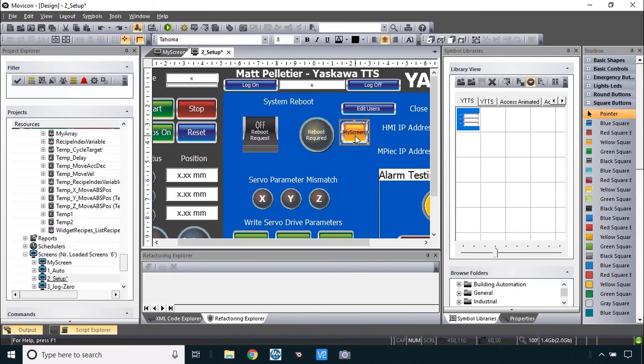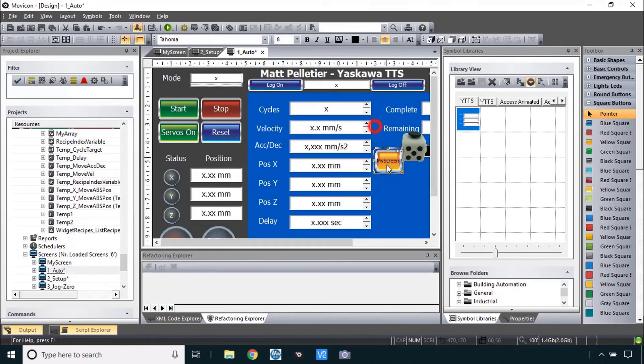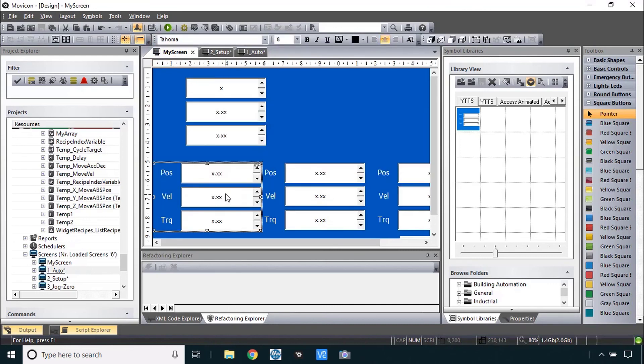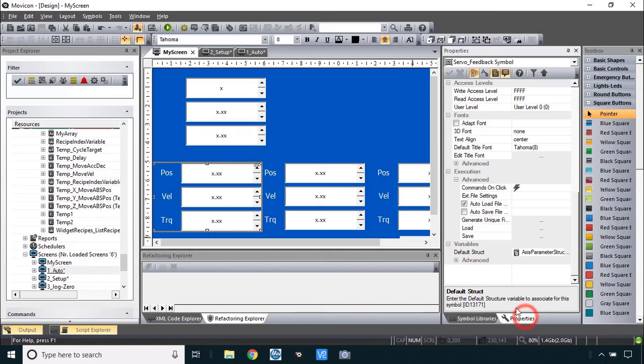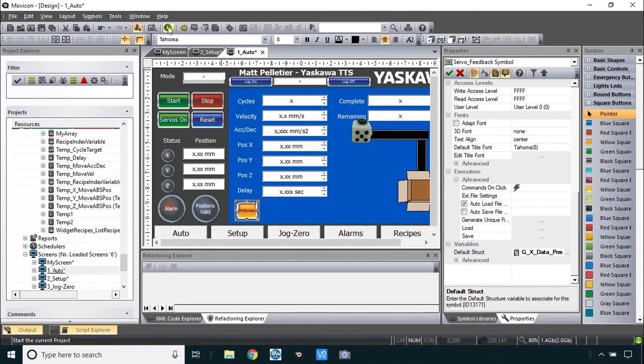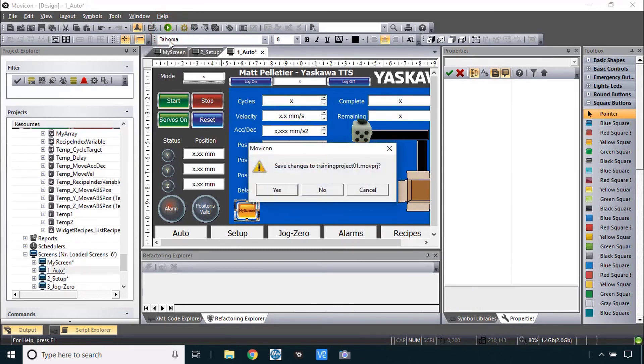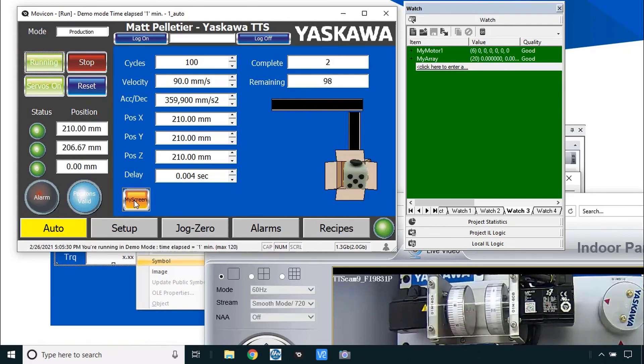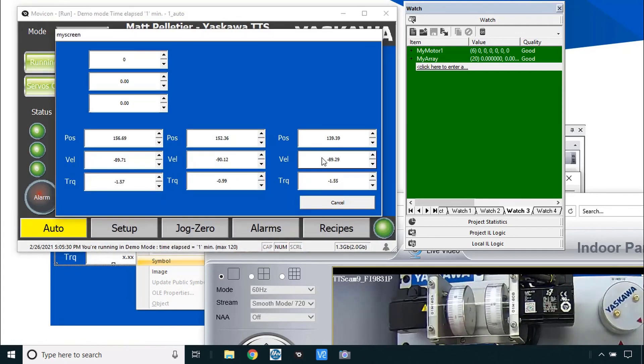To make this work better with the hardware, I'll make a button to open this screen. From the setup screen I'll add a button labeled 'my screen' with a command on release to open the screen called 'my screen' as a pop-up. Actually this button should be on the auto screen so we stay in production mode, so I'll cut it from setup and paste it into the auto screen. I also remember the first symbol was the template and never had GX data PRM assigned, so I'll go to its properties and set GX data PRM.